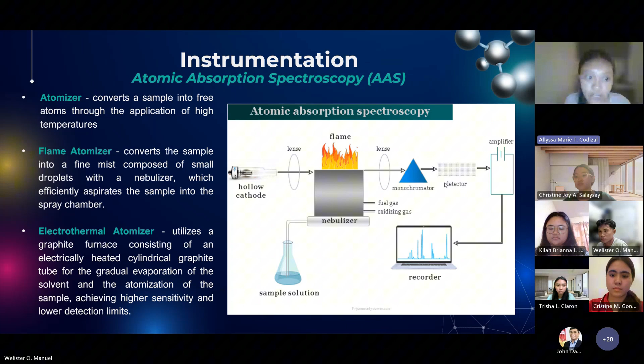Second, we have the radiation source, which is responsible for emitting light that will be absorbed by the atoms of the sample. We also have 2 types, which are line sources that emit light at very specific wavelengths that match the absorption lines of that target metal. An example for this is the hollow cathode lamp, which is a commonly used light source that produces light at specific wavelength corresponding to the element being analyzed, resulting in the excitation of its electrons. Second is the electrodeless discharge lamp, which is a more intense source that provides stronger light for better detection of some elements.